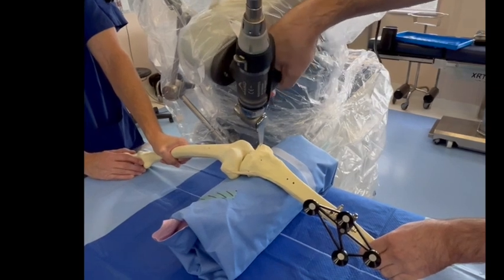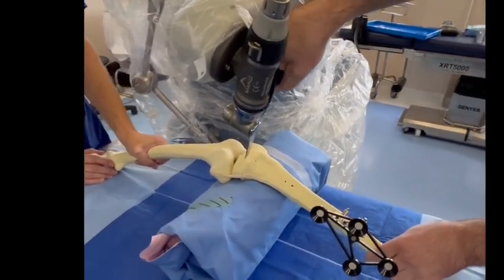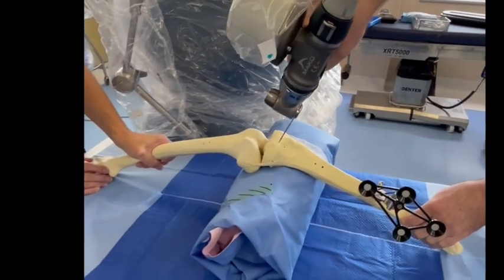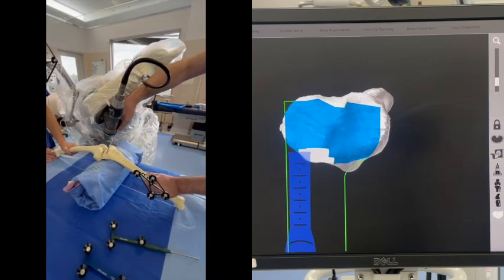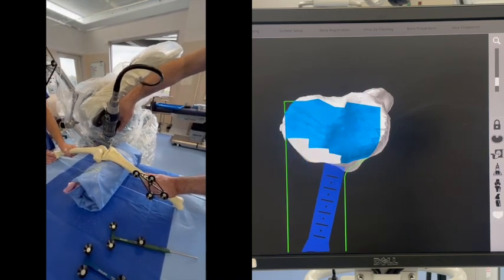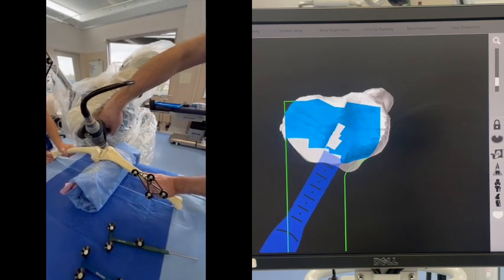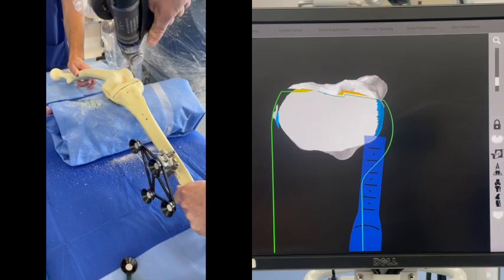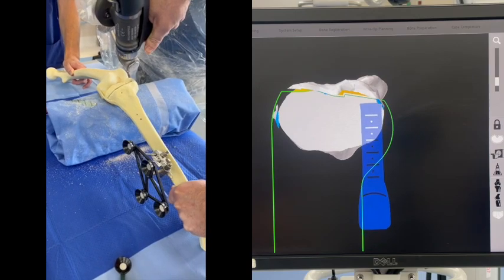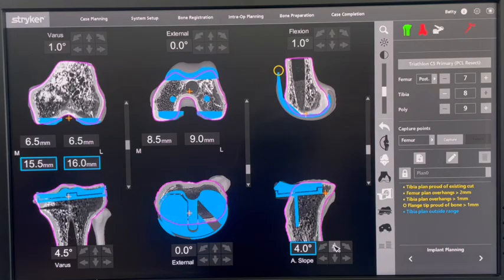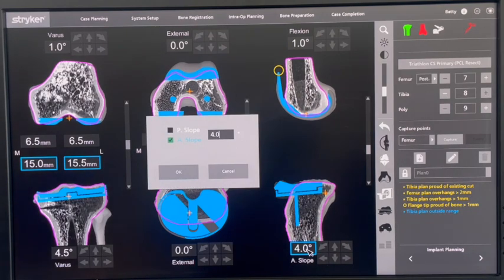Depressing the trigger positions the robotic arm to the plane of the first osteotomy. The saw blade cannot deviate from this plane. After confirming base plate position and a sagittal cut angle of 4 degrees, the first cut is made. Although currently designed for knee replacement, haptic boundaries can be customized to account for the patellar tendon in completing the cut laterally.